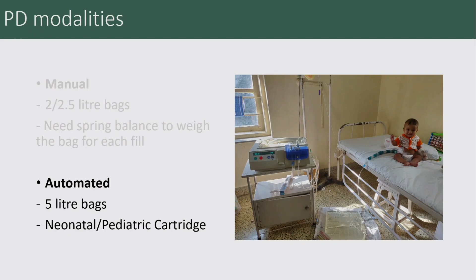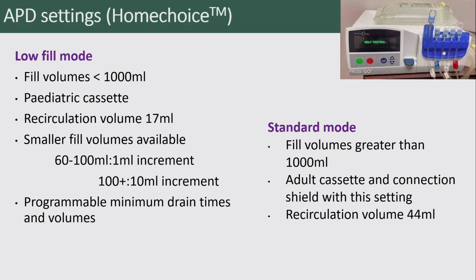Okay. Dr. Pankaj, would you like to summarize the fill mode and standard mode which are available in the APD machine which we have? So the standard mode can be managed with an adult cassette, where at one time 1 liter can be infused. But if we need a smaller fill volume, that is low fill, we have a pediatric mode, a pediatric cassette available. The pediatric cassette has very good accuracy, starting from almost 1 ml increments, particularly if it is less than 100 ml, and if it is more than 100 ml, the increment is in the tune of almost 10 ml. So we can accurately guide how much volume has to be instilled, and at the same time the recirculated volume is also minimal in low fill volume. So for a smaller kid, that definitely has an added advantage.